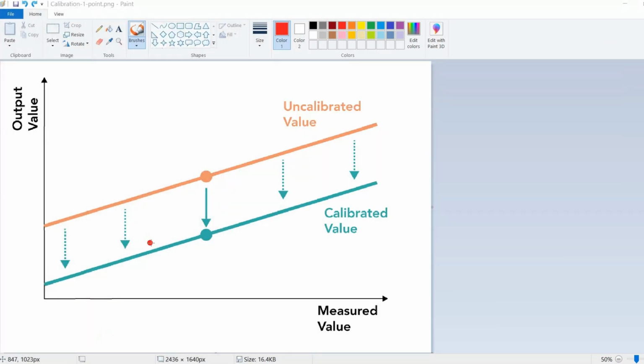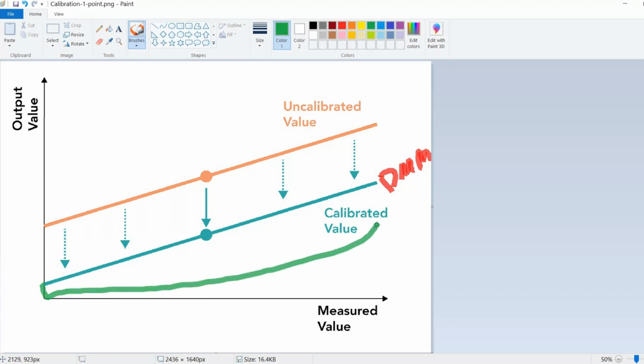To calibrate it, we have two ways of calibration. First we will go with single point calibration. So here I drew some lines for you to understand the single point calibration. Let's say here is our data. This line represents our raw data before calibration, the raw data measured. But from the multimeter, our reference, the DMM, the digital multimeter, shows us that the correct value should be in this area.